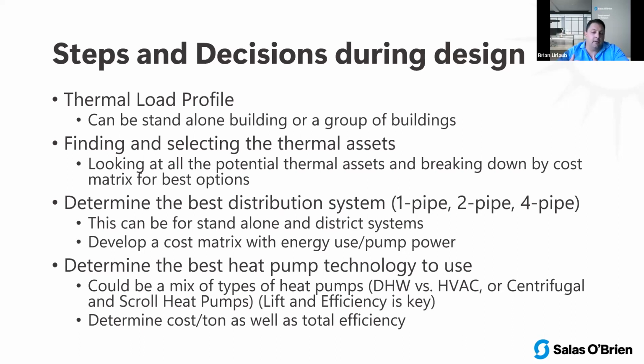What I'm going to show you today is what our company has been moving towards, called TRNSYS. It's a very dynamic modeling tool where you can put in all the different components and source energies, write dispatch models, and really model a true system and how it's going to operate. That's critical because the ground loop tools we have today work great for a single building with a distributed heat pump and a ground loop—GLD, GLHEPro all work well. But when you start mixing and matching different COPs and EERs of heat pumps, they don't let you break those out based on the load profile and how much each system is putting into or taking out of the ground loop at different times of the year.